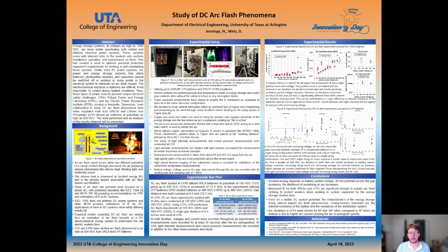The study of light intensity measurement, primarily conducted at UTA, employs light measurement devices similar in wavelength response to a human eye. Sound pressure measurement is taken from about 24 inches away from the arc. High-speed video of the arc inside the box is recorded. High-speed thermal imaging is recorded of the calorimeter board. And battery voltage across the gap, and current through the arc, is also recorded using an oscilloscope at sampling rates of higher than 1 megasample a second.